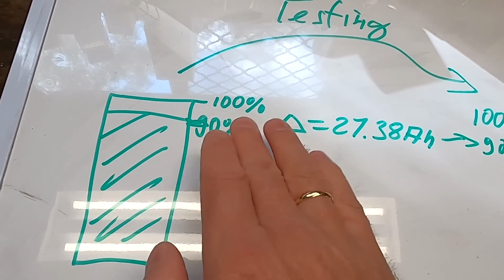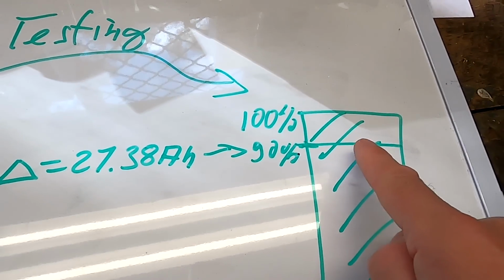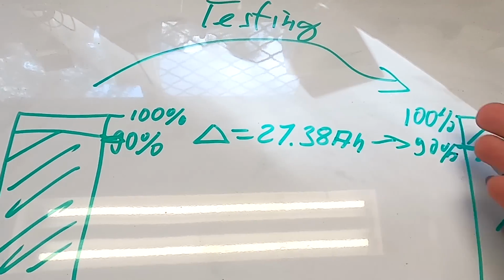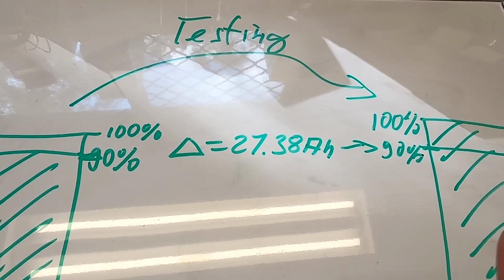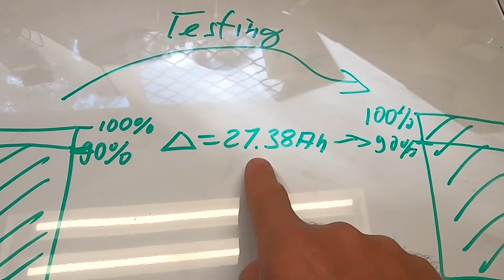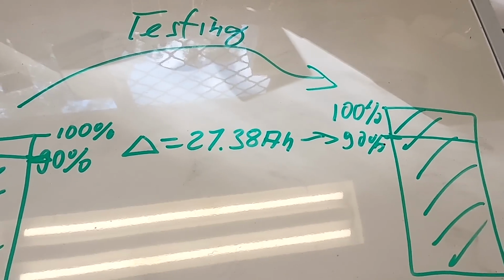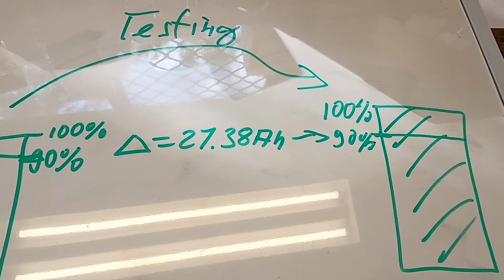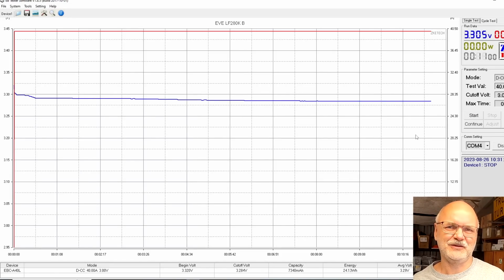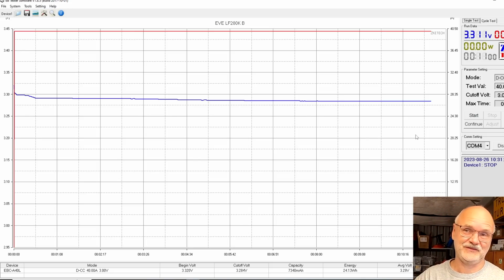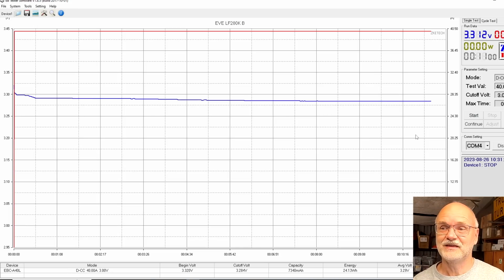Otherwise, we would have all the batteries sitting on 90% because we haven't used them, and just this one battery is on 100%, and we would have a huge imbalance, and we don't want that. So we have to discharge with 27.38 ampere hours. It doesn't need to be 100%, we're just getting the battery back to the same state of charge as before we started all this testing. That was the main purpose of discharging 27.38 ampere hours.